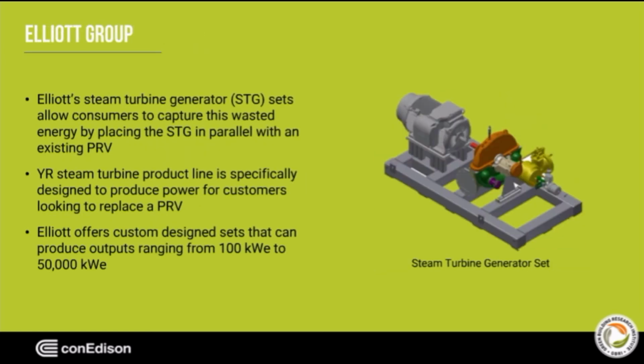Elliott Group is another manufacturer that designs and manufactures steam turbine generator sets that allow customers to capture energy that is wasted through an existing PRV. Elliott Group allows customers to custom design a steam turbine generator set that best fits their steam load profile. They have a steam turbine product line that is specifically designed to produce power for customers looking to replace a PRV. These custom designs come in a variety of sizes that will produce a range of electricity depending on how large your steam load is. Elliott Group will work with each customer to find the right steam turbine generator set to best fit their needs.